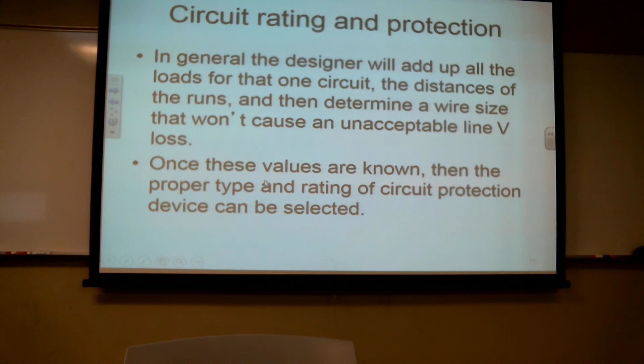The other thing about circuit protection is you need to be conscious of what behavior the circuit protection enacts itself. In some cases, you might have a situation where you get some transient. Every time I hit transmit on the radio, the current value is going to go way up. Because of that, I might want a current protection that takes a little bit of time. And remember, even with a fuse, doesn't the fuse have to heat up before it blows? Yeah. So there's going to be a finite amount of time, and that time is going to change depending on how much current you're hitting it with.